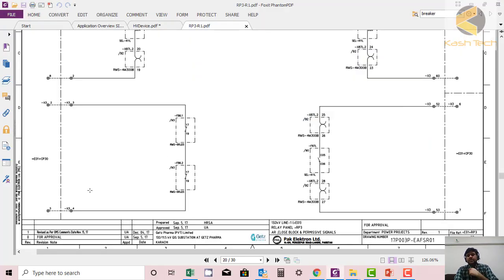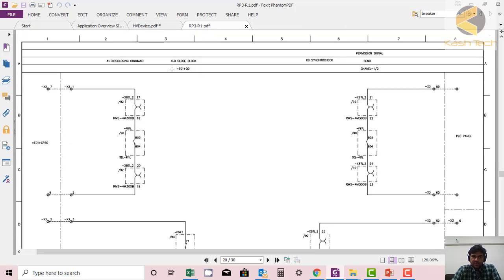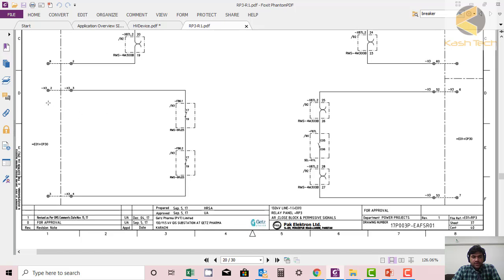Let's see how the lockouts are implemented in the drawing. I have opened the protection panel drawing in RP3. In this one you can see close CB, close block is mentioned here and this CB close block is for E01 plus Q0. You can see the closing supply which is basically controlling supply for the breaker.